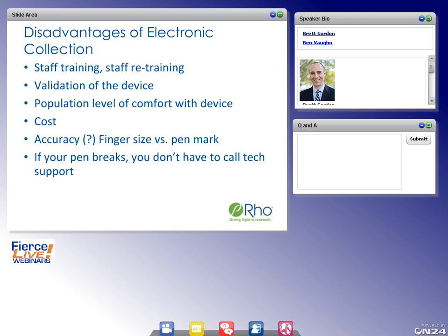Now, some devices do allow you to make your initial mark and then you can kind of slide it back and forth if it's not precisely where you wanted it. And how that works is for a 100 millimeter VAS, there's 101 stops from 0 to 100. So the actual size on the screen might not be 100 millimeters, but there's an equivalent number of stopping points.